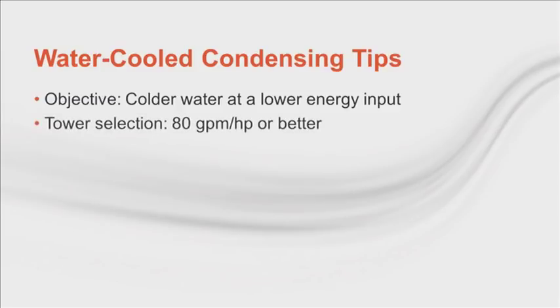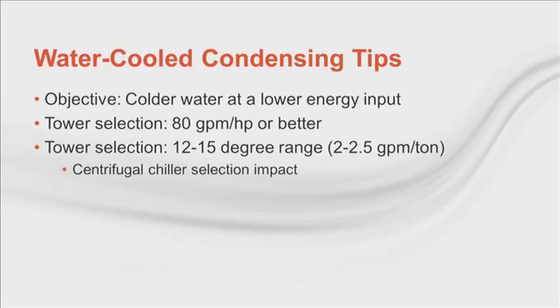We think 80 GPM per horsepower is achievable for tower selections, nearly twice the efficiency of the axial cooling tower minimum code requirement. For the range, that is, the difference between the entering and leaving water temperatures, 12 to 15 is appropriate. This equates to 2 to 2.5 GPM per chiller ton. This will affect the centrifugal chiller selection, so ideally the chiller is also new or being replaced.